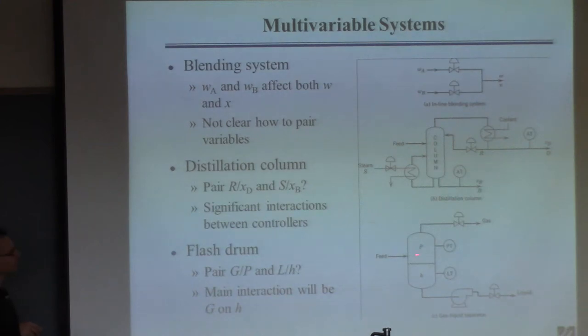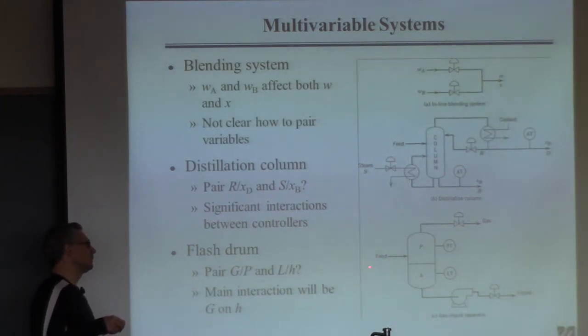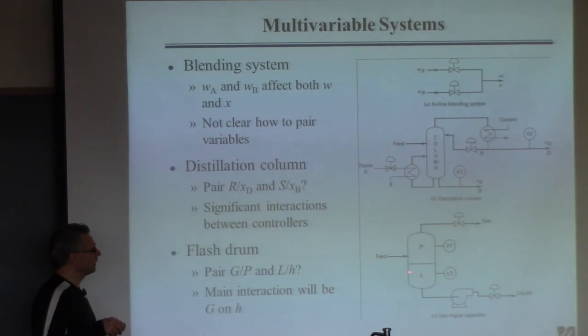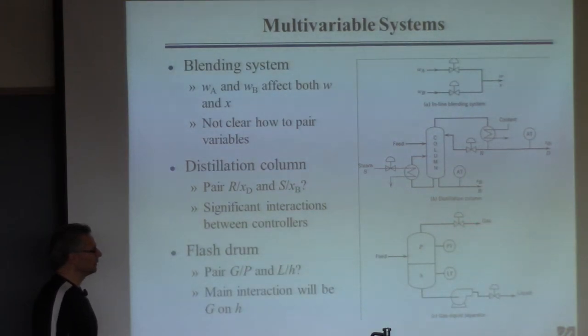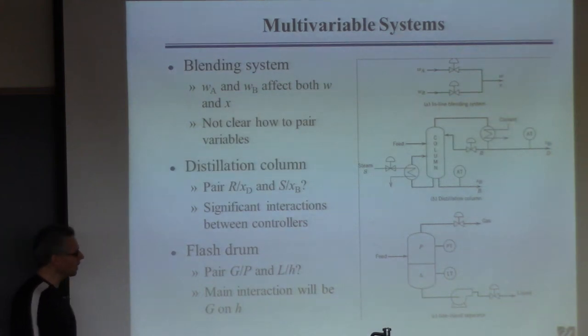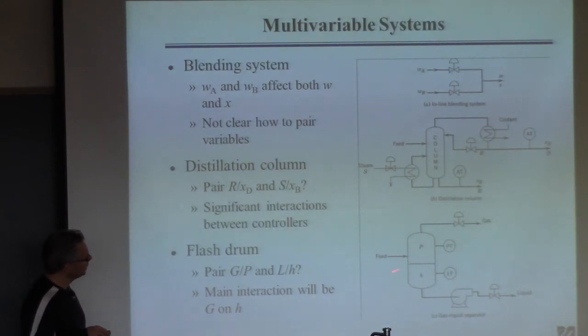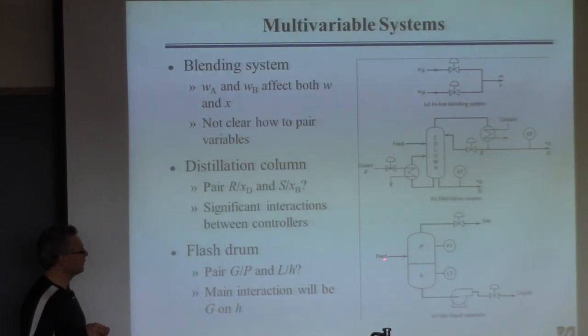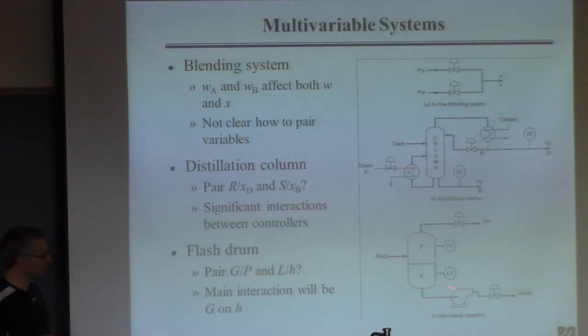For a flash drum — where you heat a stream, expand it into a drum, and create vapor and liquid — you want to control the pressure, because pressure affects the VLE of the separation, and also the liquid level, to maintain inventory. You can manipulate the gas and liquid flows coming off the drum. Intuitively, the gas flow has a more direct effect on pressure, and the liquid flow is the direct way to control level. However, changing the gas flow will also affect the liquid level through VLE, causing interaction between controllers.